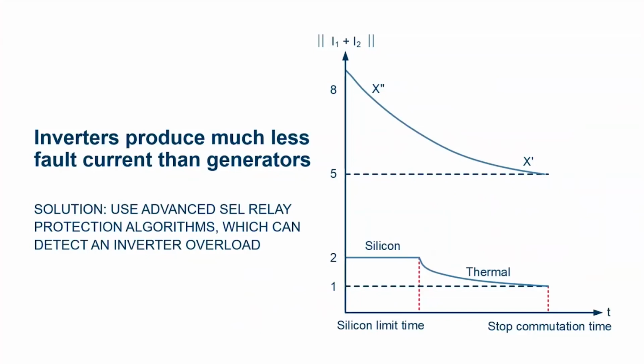That is a complete shift in how to think about even detecting faults. Can you, for example, see if a tree has fallen on your power line? It can be quite challenging with an inverter because, in this case, the same size 1 MVA inverter next to a 1 MVA generator is going to produce momentarily, for just a few milliseconds usually, 2 per unit current. And that falls off quickly, and then the inverter actually commonly stops commutation. You don't want that. You want the relay to clear the fault before the inverter shuts off. It's a challenge you can solve with advanced algorithms in an SEL relay.